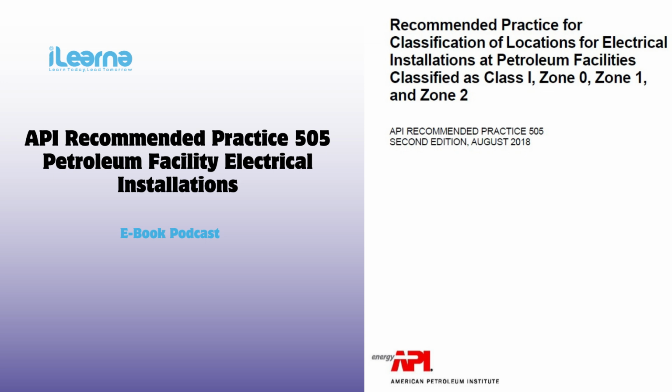Absolutely not. So how does API 505 actually work? Does it lay out specific rules for every single piece of equipment? Well, not exactly. It's more about classifying the location itself based on the risk level. Like how likely is it that there's going to be a flammable gas or vapor in that area? And then once you know the risk level, you can refer to other standards to actually choose the equipment. So it's a kind of two-step process. Yeah, you could think of it like that.